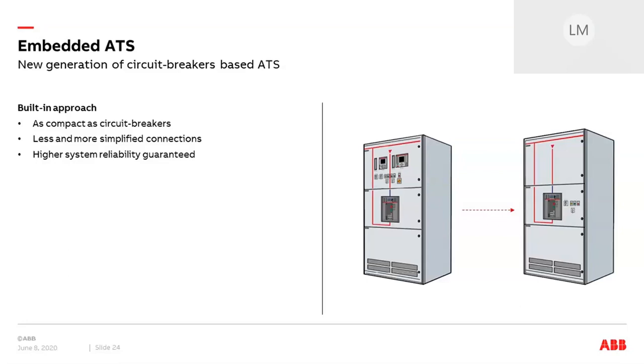This built-in approach, combined with the high computing power and capabilities of the Ekip trip units, represents a distinctive feature of EMAX2 in the market. Thanks to these integrated capabilities, the embedded ATS solution can be as compact as EMAX2 is — nothing more is needed — meaning space savings in the electrical installation as well as fewer and simplified connections. Less components also imply higher system reliability, which is further increased by EMAX2 circuit breakers that can be equipped with protection trip units that periodically check the continuity of connections and the presence of faulty conditions.